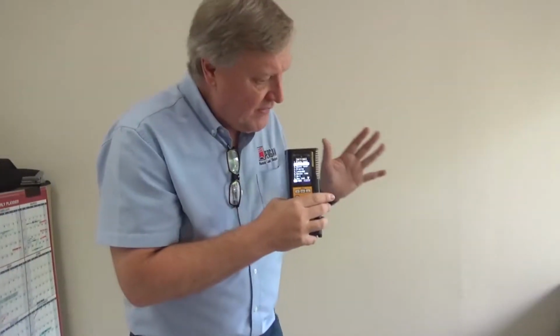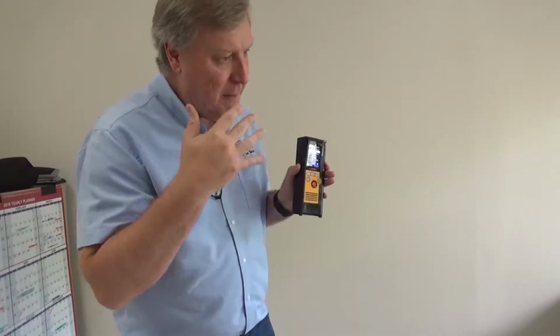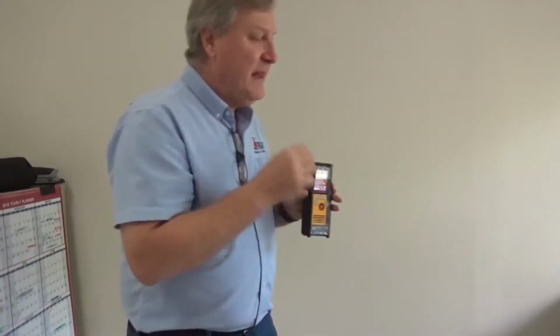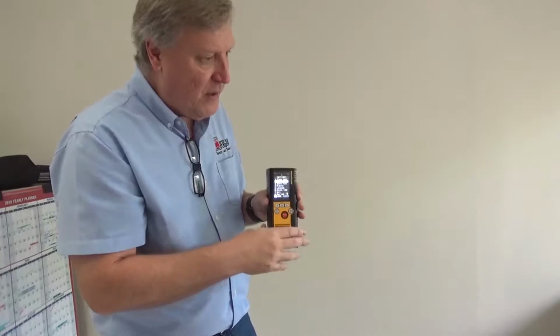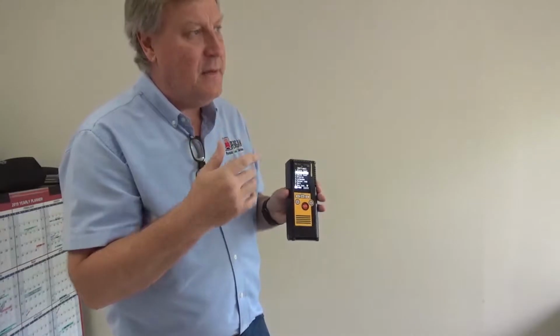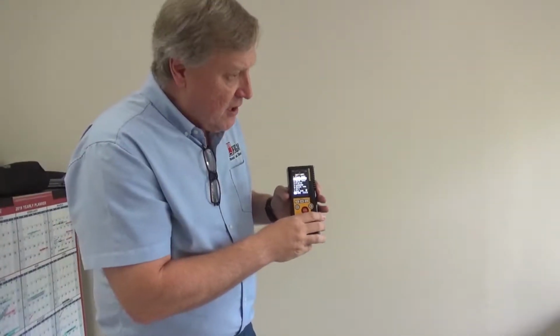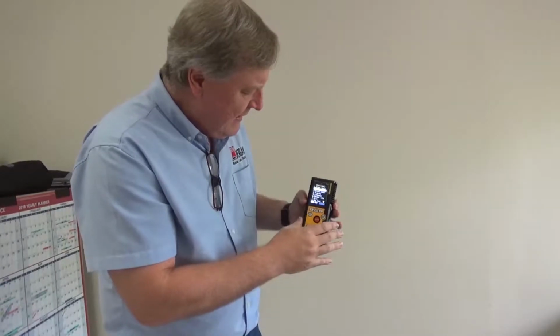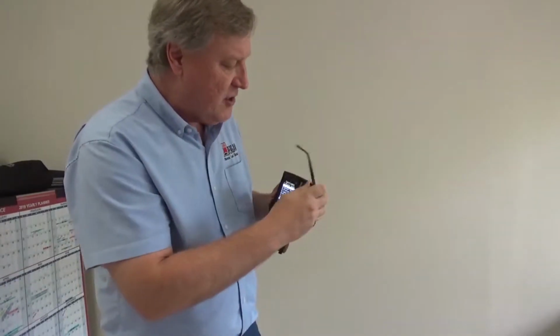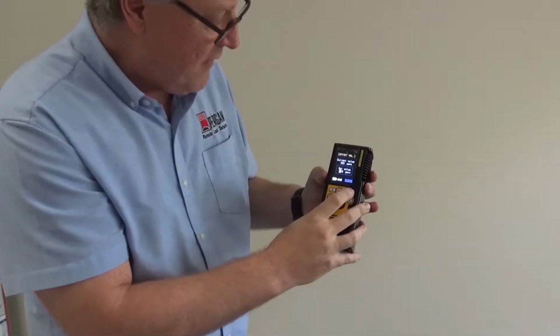Lasers by nature, from a physics standpoint, like flat surfaces. They like flat concrete. They don't like mud necessarily. They don't like broken concrete. They don't like gravel. They don't like tall grass. Occasionally, when you're out in a distribution environment, these lasers will give you an indication as if there is methane there, but it's really just a laser bouncing improperly off a surface on the ground at a distance. And with this instrument, you can actually mitigate the chance of getting one of these false positives.